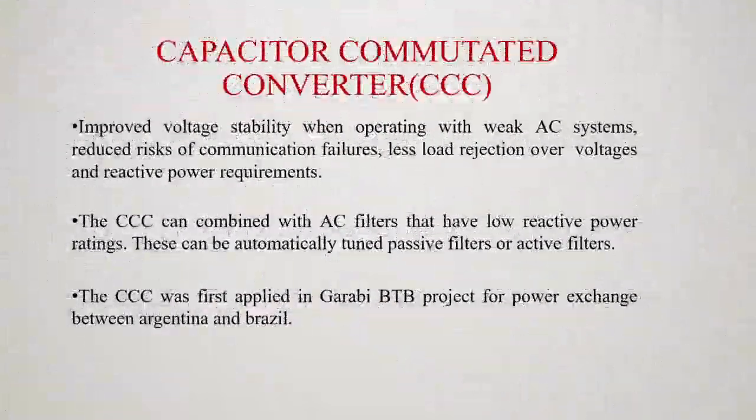Next is capacitor commutated converter, CCC. This involves the connection of commutation capacitors in series with the valve side windings of the converter transformer. This is not strictly a new technology and has been studied under the label of forced commutated converters.